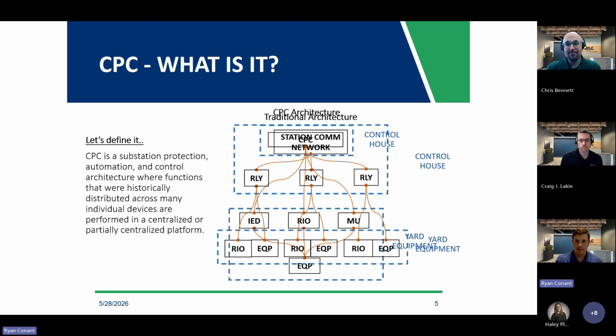Most of us think about substation protection and control systems. We think about a dedicated IED that's assigned to an individual bay, breaker, transformer, or bus, like shown on the graphic on the screen here. CPC will really change that model by moving more of those functions into a centralized computing architecture that will typically be communication-based. IEEE has described CPC as the next generation approach for substation P&C systems.